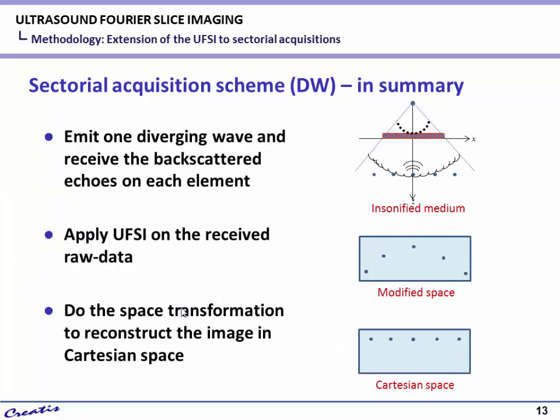Then we apply the sectoral acquisition scheme: you emit one diverging wave to insonify the medium and receive the reflected echoes on each element. Then you apply the ultrasound Fourier slice algorithm directly on the raw data, reconstructing the image in modified space. You can see there will be a distortion of the image, and then you need to do the space transformation derived previously to get the image in Cartesian space.